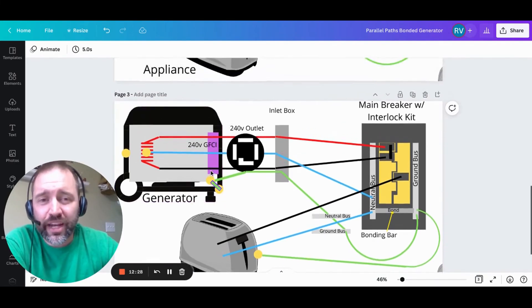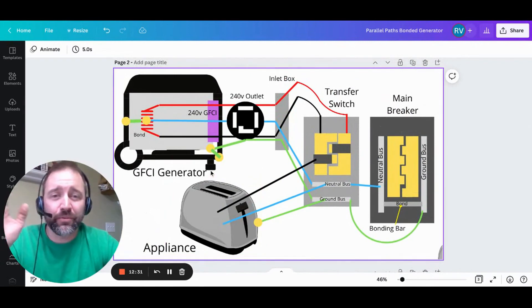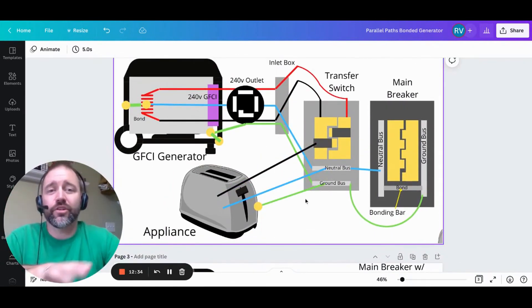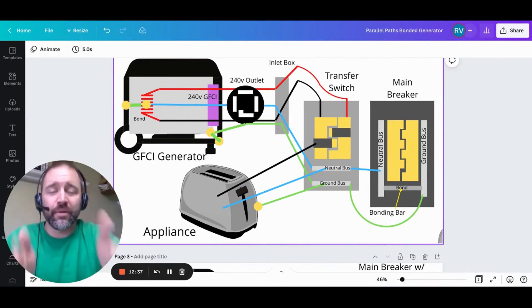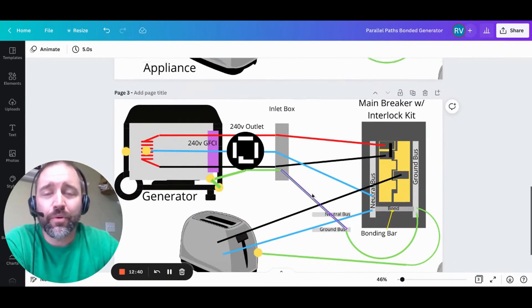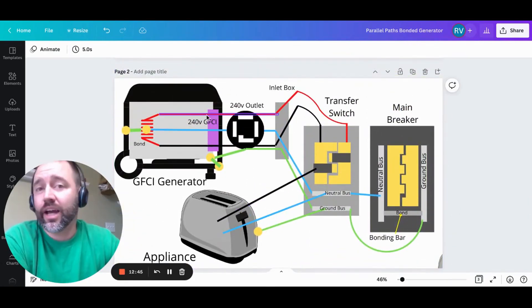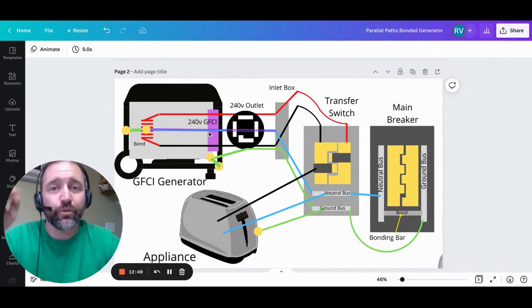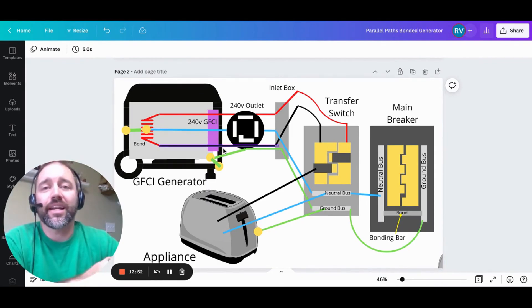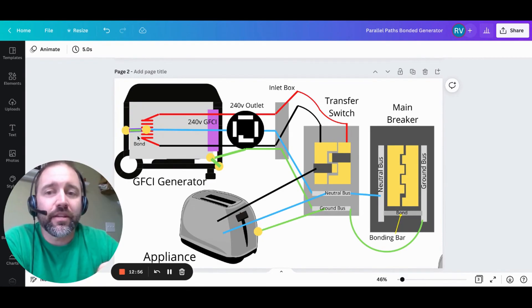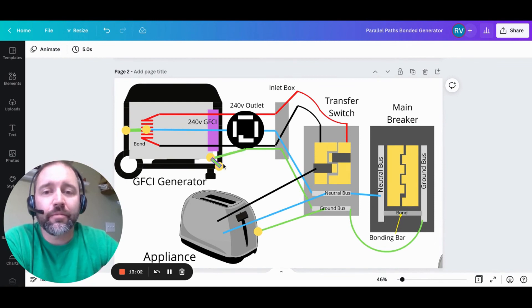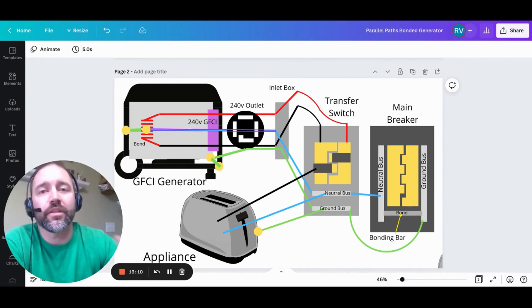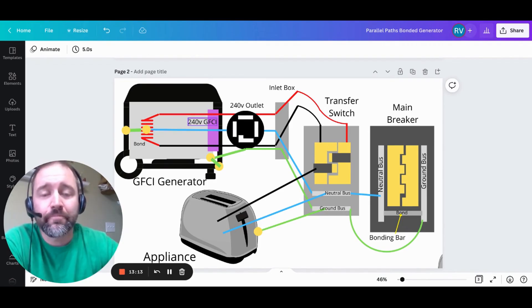So hopefully this helped you out in understanding what's going on with your particular situation. I kept it really rudimentary. We could hook up additional toasters and run electricity off of both of the buses inside of the transfer switch or on the main breaker here. But it's going to be the same. Yes, you're going to have some current going out and returning on the hots with a 240 volt system here and then the difference between the two traveling back on the neutral. We're not going to get into the weeds of that. Basically, either way you slice it, if you have this bond here on the generator and the bond here in the house, you're going to have some of the current coming back on the ground and it's going to be completing the circuit here instead of through the GFCI. That's always going to create an imbalance and that's always going to trip your breaker and you won't be able to get anything done.